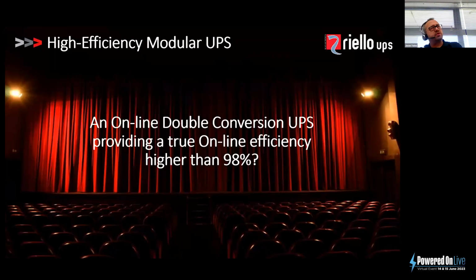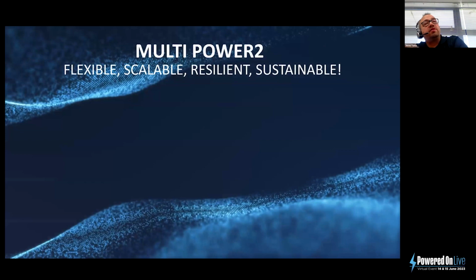Now, this is not so much a sales pitch, but just to show you a typical system that is available in the market. This is a high efficiency modular UPS system that's produced by Riello UPS. It's an online double conversion system, and it will provide a true online efficiency, so this is permanently online mode, higher than 98%. The system is the Multi-Power 2, based around a flexible, scalable, resilient, and sustainable UPS system.